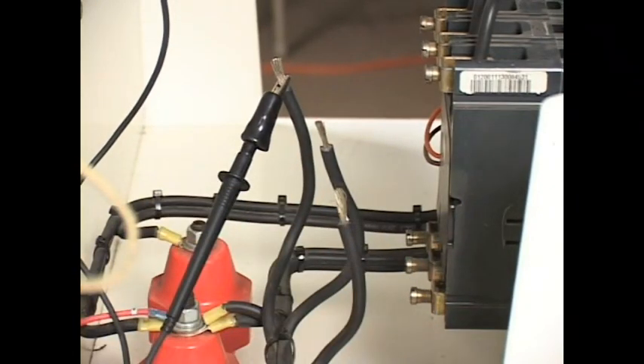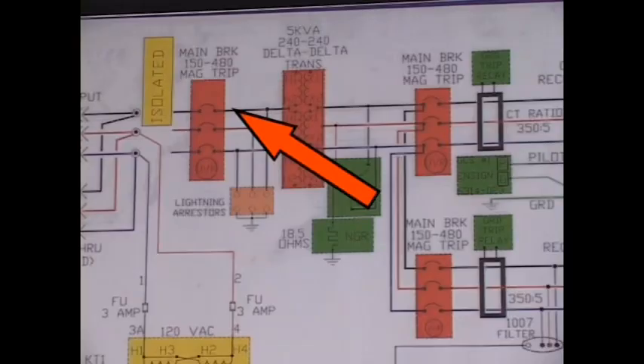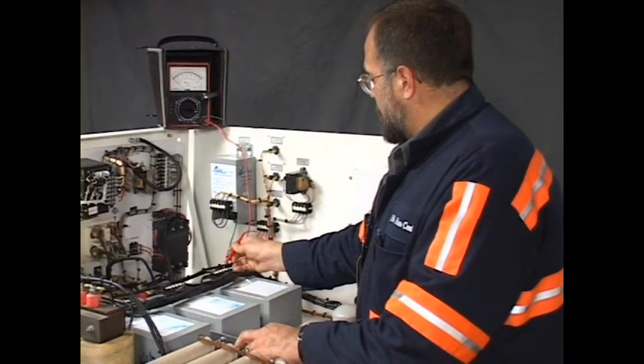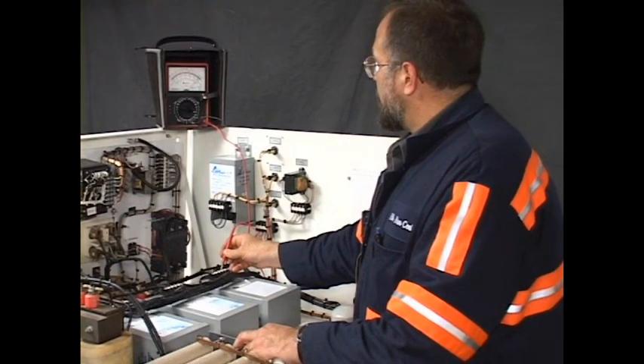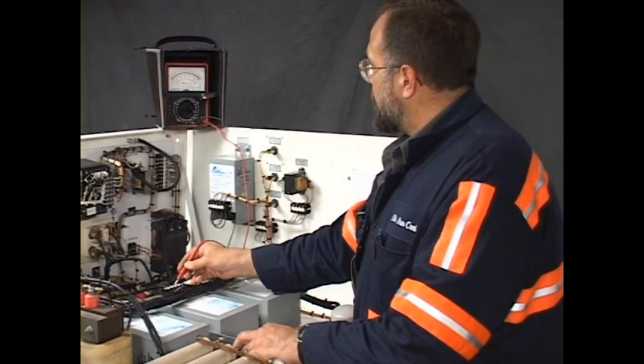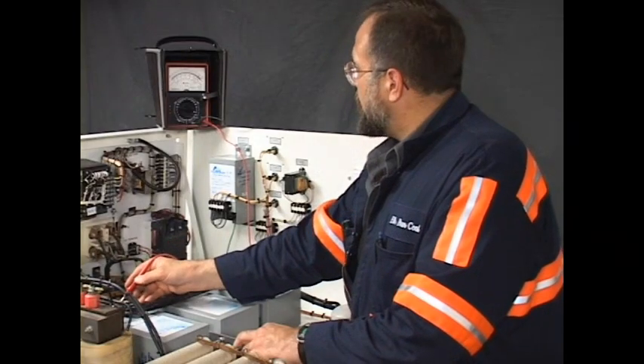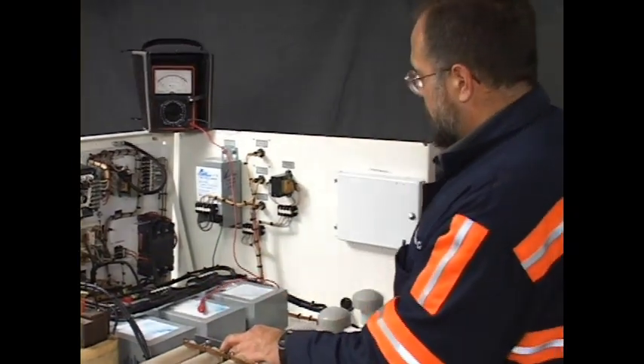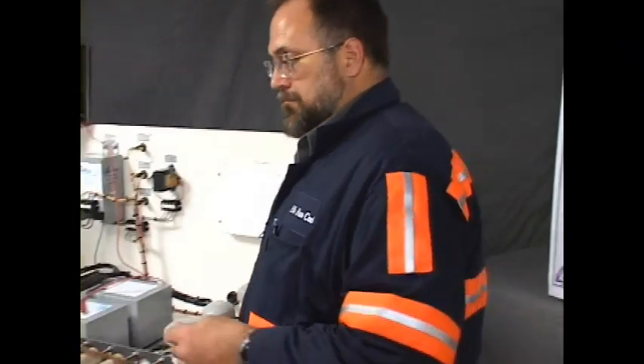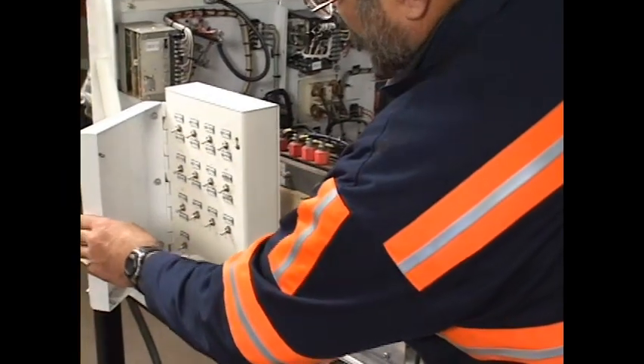Now the last phase would be this one. We have continuity, we have continuity, and we have continuity. Now that illustrates proper reading. That's how the circuit should read. Now I'm going to install the problem by flipping a toggle switch in our test panel and make the same checks again, find our problem. Problem number 61.